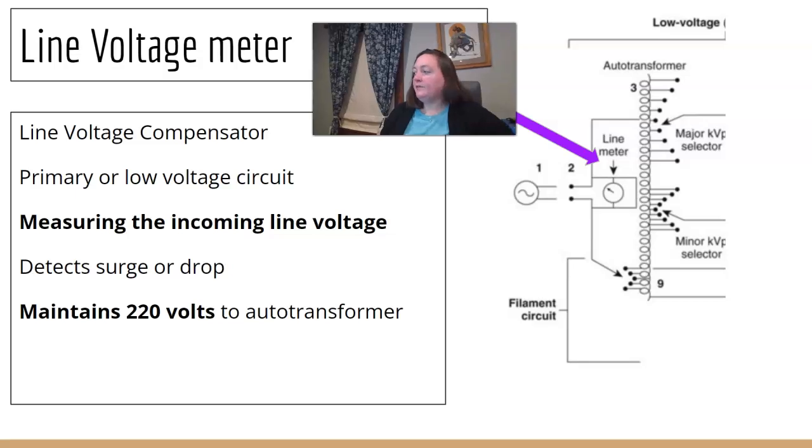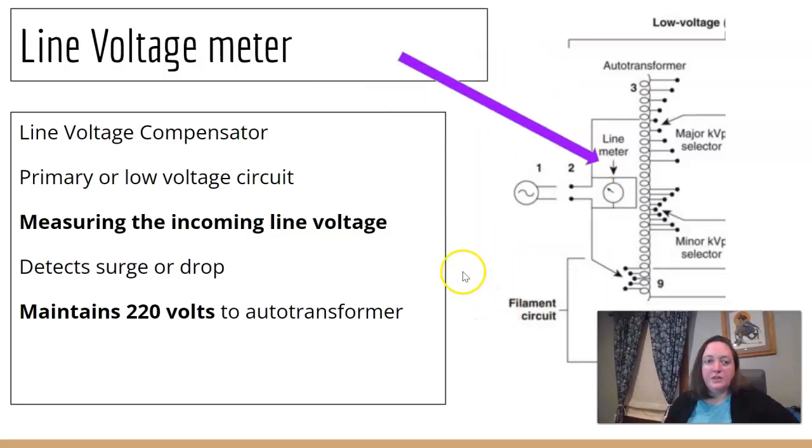There is a line voltage meter, which is sometimes called line voltage compensator. And it does what's in the name. It compensates. It's going to measure the incoming line voltage. And if it detects a surge or a drop, it's going to maintain those 220 volts for the auto transformer. And that's the first transformer that we hit in the circuit.